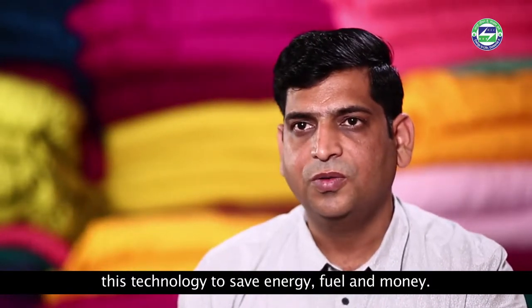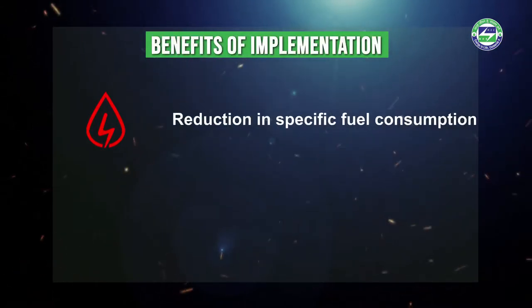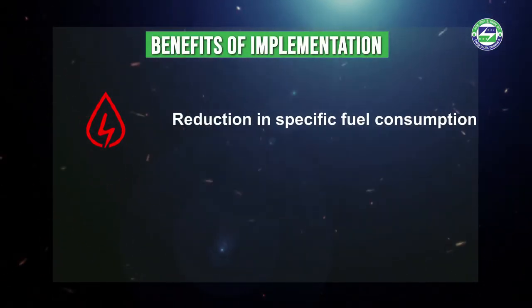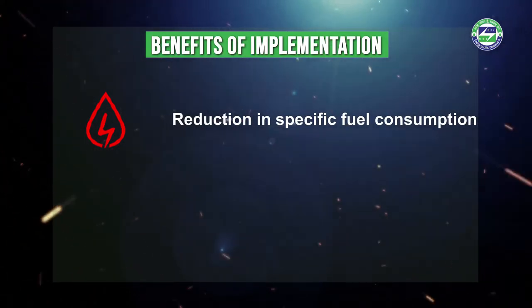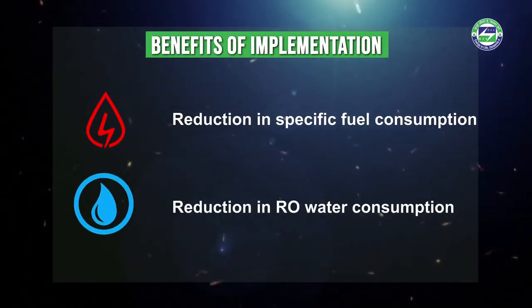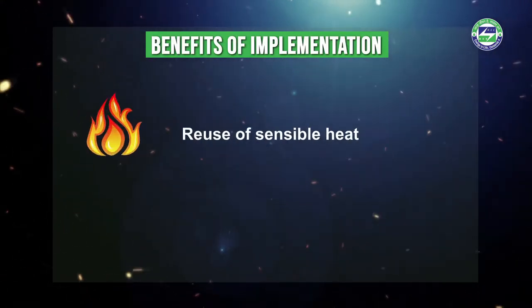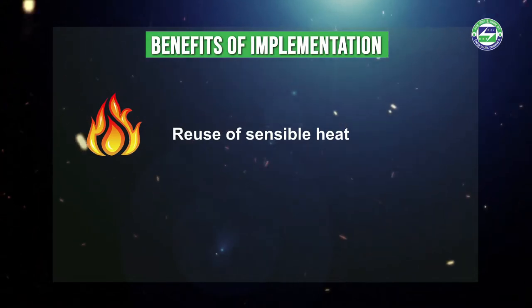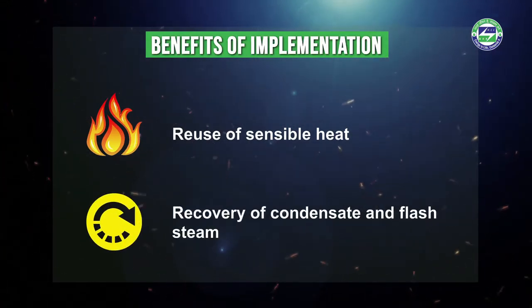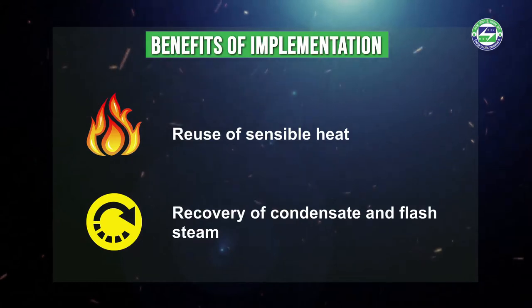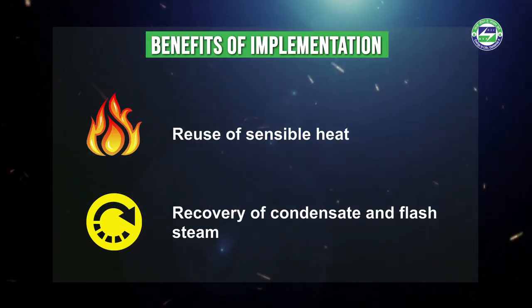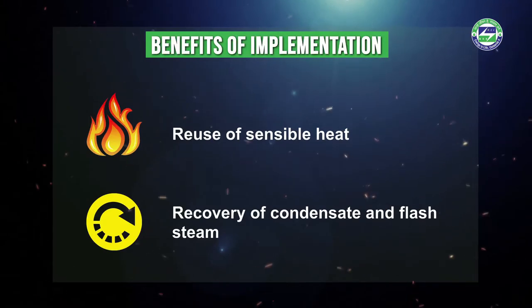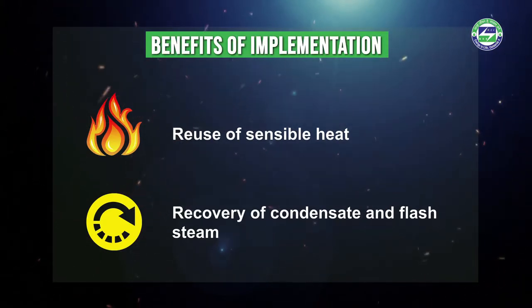The implementation of the condensate recovery system leads to a two to three percent reduction in specific fuel consumption, fifteen to twenty percent saving in annual RO water consumption, and reuse of sensible heat which would otherwise be lost in condensate. The installation of the system will allow eighty to one hundred percent recovery of condensate and flash steam formed during the jet dyeing process.